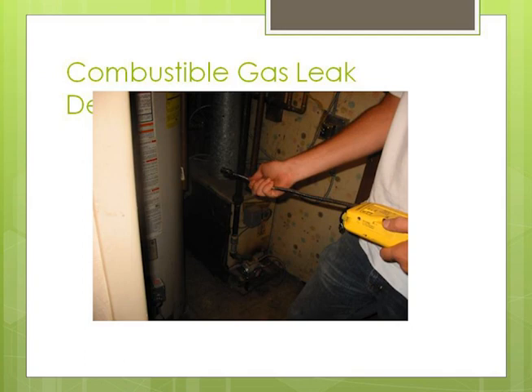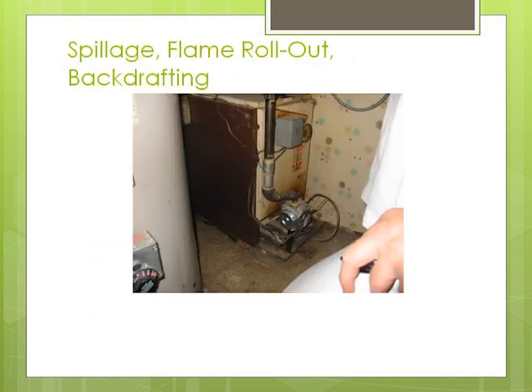Next slide: combustible gas leak detection. This is the unit — you just run it along the gas pipes and it beeps if you have a gas leak. For spillage, flame rollout, and backdrafting — you can see the burnt area at the bottom of what may be a boiler. If you look at your hot water heater at home and it looks burnt around where the flame is, then you've got problems with depressurization around that room and you should take care of that.